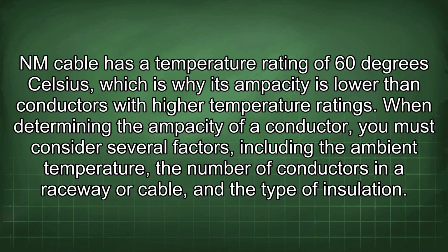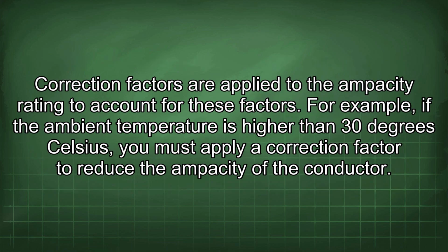When determining the ampacity of a conductor, you must consider several factors, including the ambient temperature, the number of conductors in a raceway or cable, and the type of insulation. Correction factors are applied to the ampacity rating to account for these factors. For example, if the ambient temperature is higher than 30 degrees Celsius, you must apply a correction factor to reduce the ampacity of the conductor.